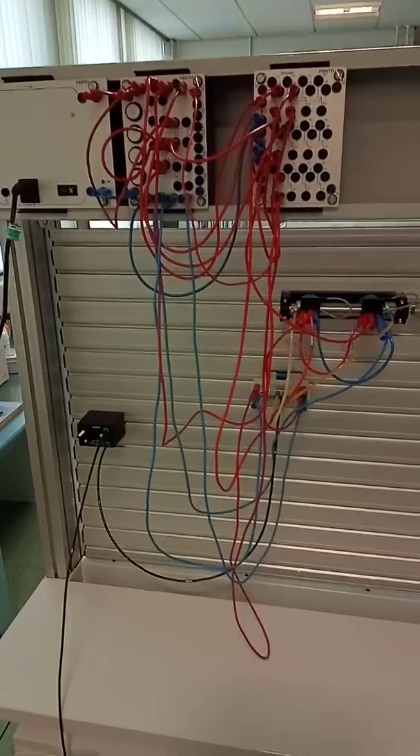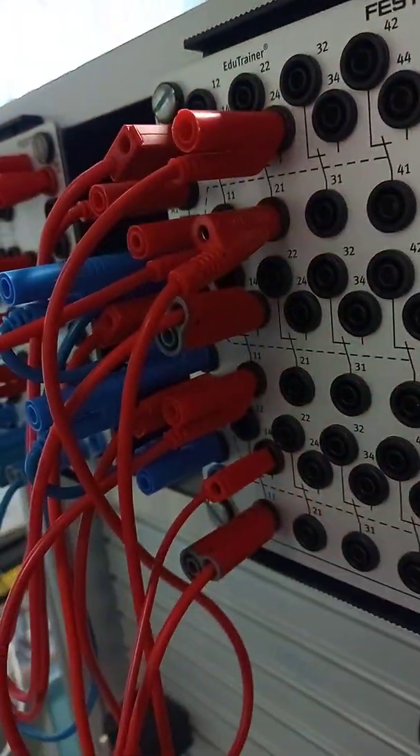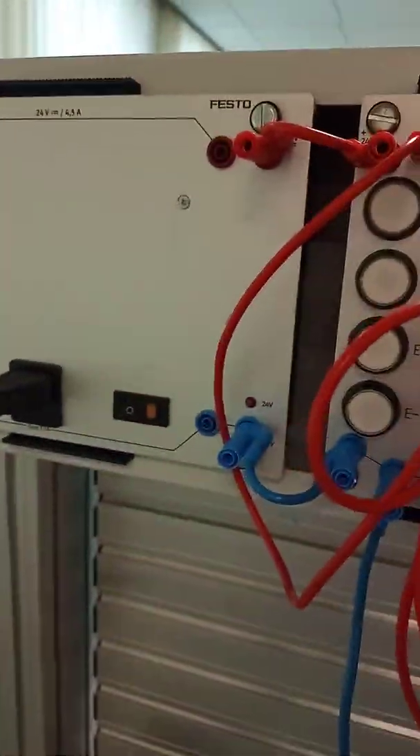Before carrying out the inspection, I would have all power off if possible. Then I would have a general look at the condition of the cables. The condition looks pretty good — no bare wires, nothing loose, nothing hanging where it shouldn't hang.